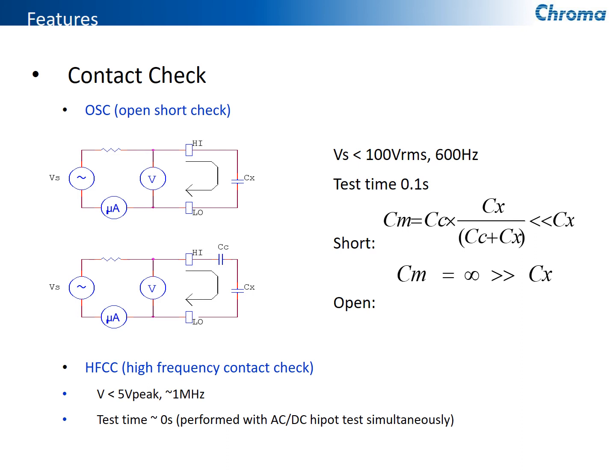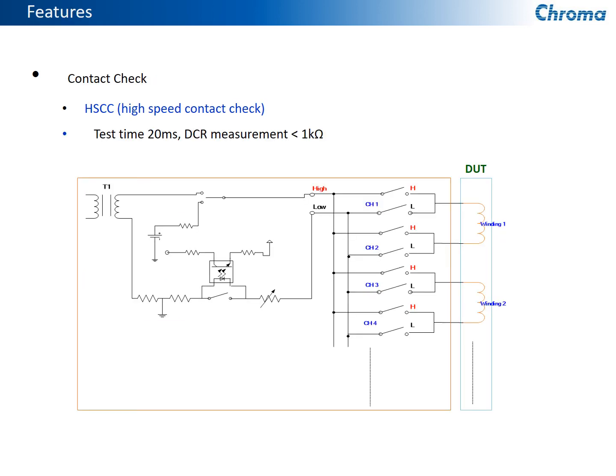In addition to that, we can detect if there's an open or a short prior to starting the test. So it's a great way to knowing that you are physically connected before you run the test and that you're connected to the unit properly. Now this only works for when you're doing an AC hipot test or for testing insulation resistance or DC hipot test. But when we're doing a test for the winding itself, such as impulse winding testing and DC resistance measurement, we can use something called a high-speed contact check.